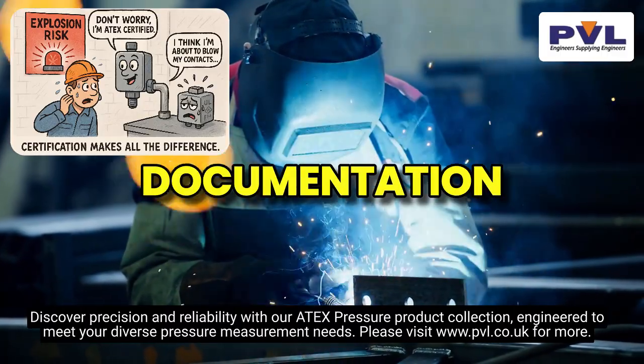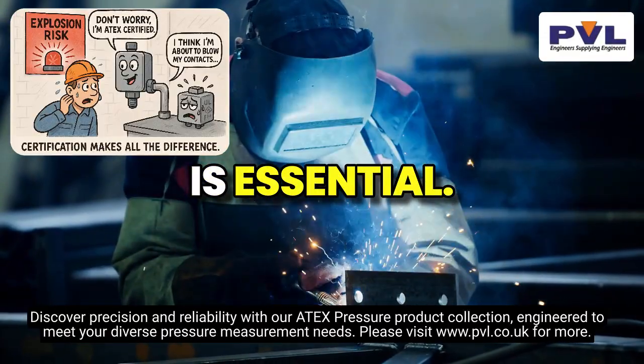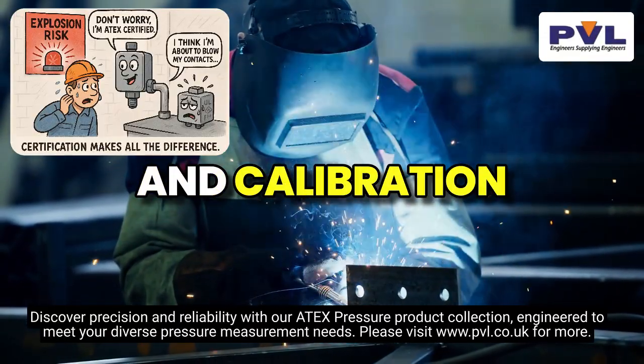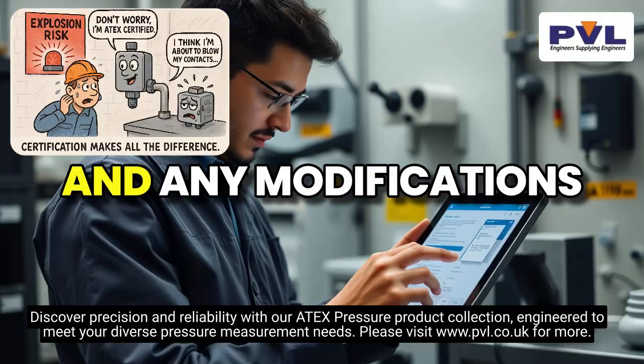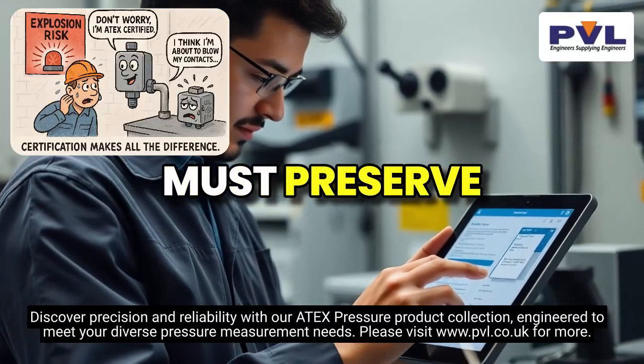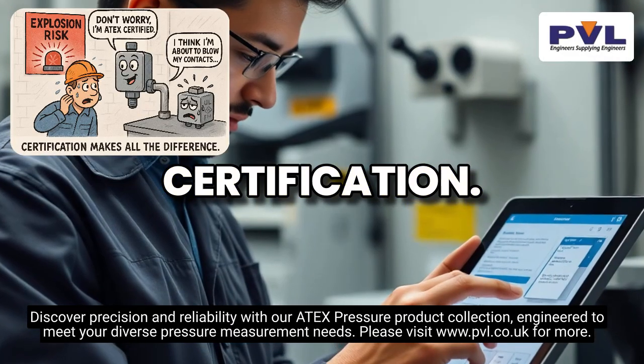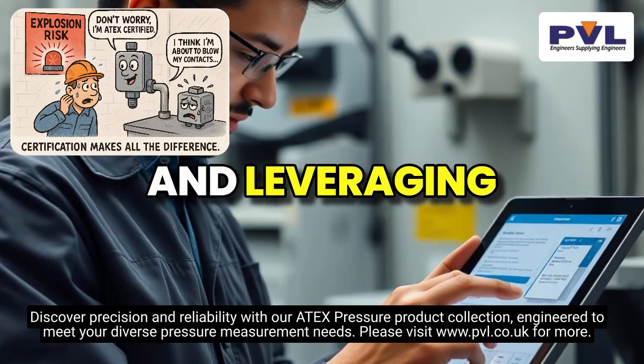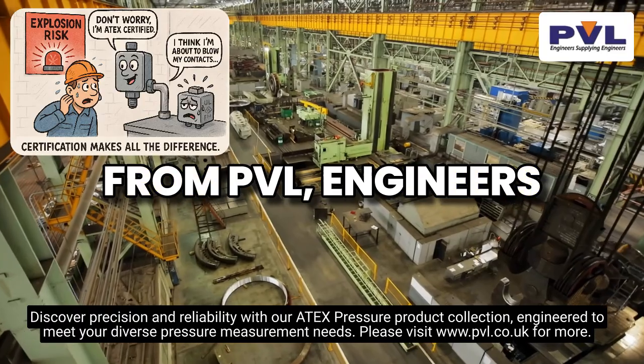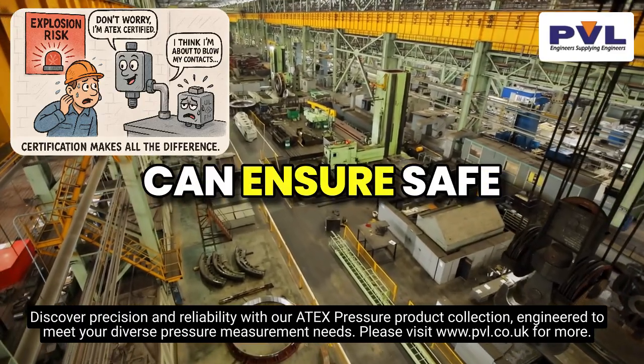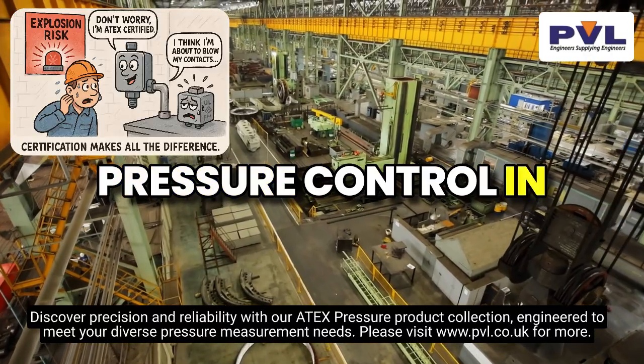Finally, maintaining documentation and traceability is essential. All certificates and calibration data should be kept up to date, and any modifications must preserve the device's certification. By following these guidelines and leveraging the certified devices from PVL, engineers can ensure safe and reliable pressure control in hazardous areas.